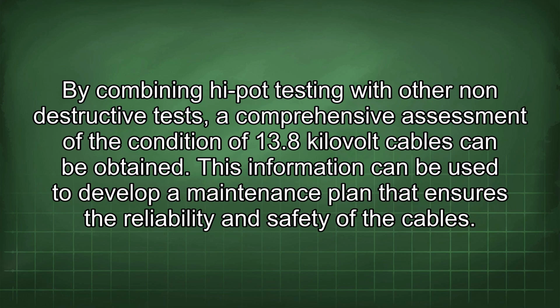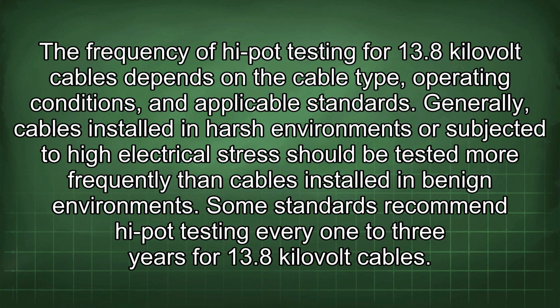By combining high-pot testing with other non-destructive tests, a comprehensive assessment of the condition of 13.8 kV cables can be obtained. This information can be used to develop a maintenance plan that ensures the reliability and safety of the cables. The frequency of high-pot testing for 13.8 kV cables depends on the cable type, operating conditions, and applicable standards. Generally, cables installed in harsh environments or subjected to high electrical stress should be tested more frequently than cables installed in benign environments. Some standards recommend high-pot testing every 1 to 3 years for 13.8 kV cables.